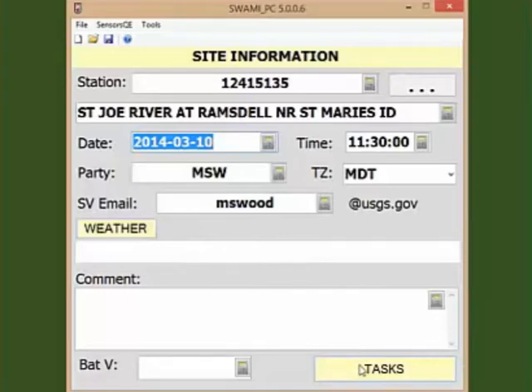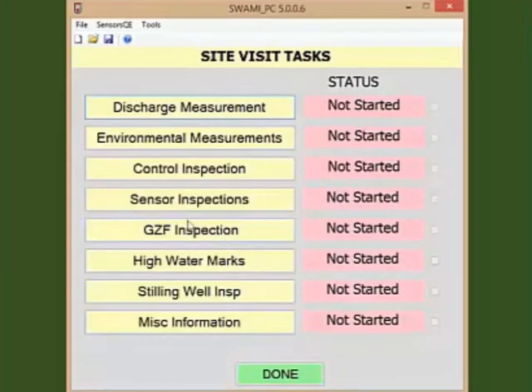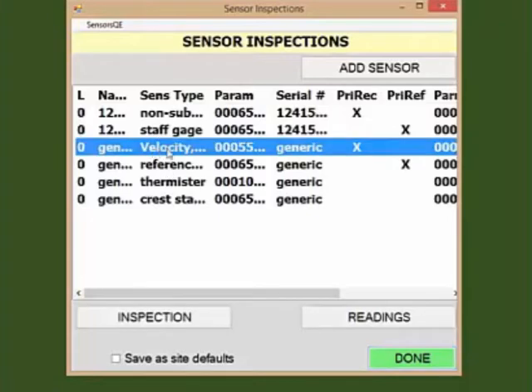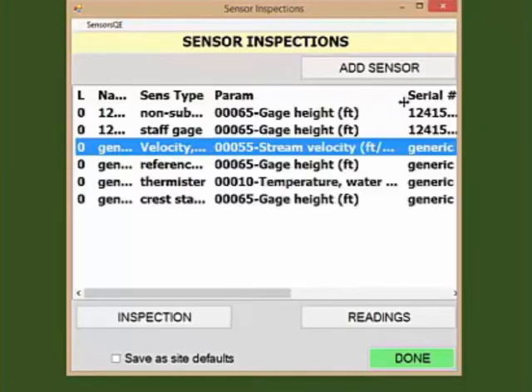Click on Tasks in the lower right corner. We are going to enter some information about the index velocity meter, an acoustic Doppler velocity meter, or ADVM. Click on Sensor Inspections. Your ADVM should already be loaded as site-specific sensors through SiteVisit and your GetSensors script. Refer to other screencasts and tip sheets on configuring sensors in SiteVisit. Highlight the velocity sensor, which is identified with parameter code 00055, stream velocity in feet per second.